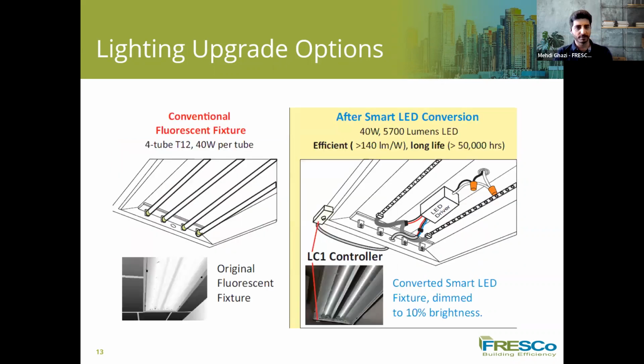Another option that we have when we replace the light bulbs is LED strips. They significantly reduce the amount of power consumption. They have a much longer lifetime, more than 50,000 hours could be their lifetime. And as I mentioned, their return on investment is quite reasonable, between 1 to 4 years, and under 2 years is better for hallways and parkades, where we have lights on 24/7.